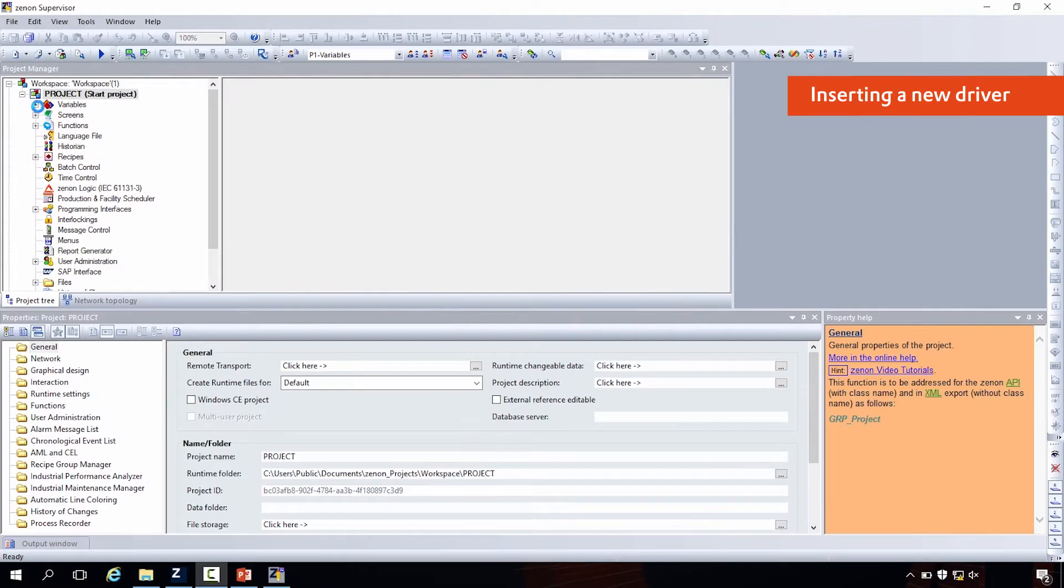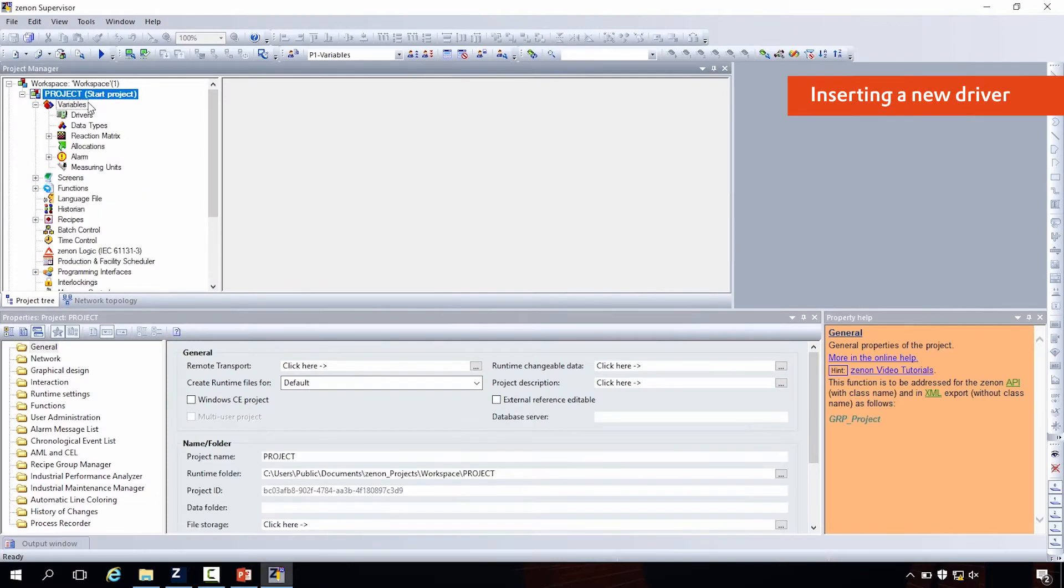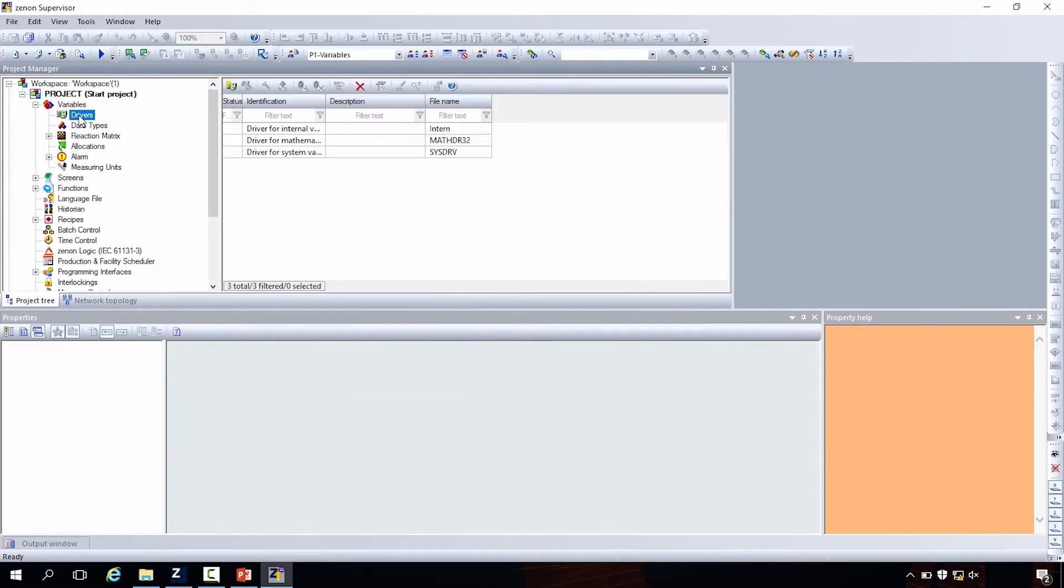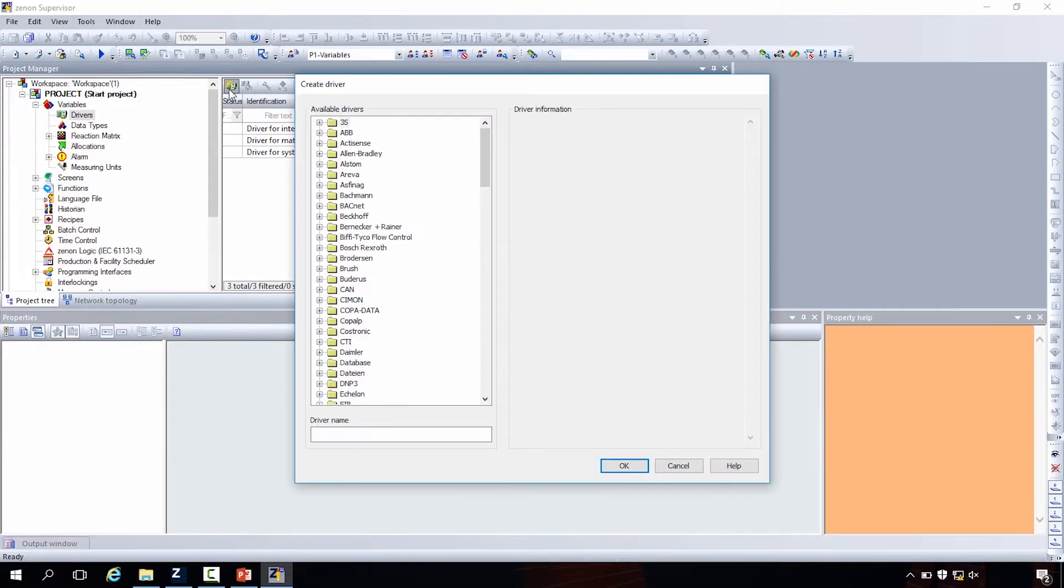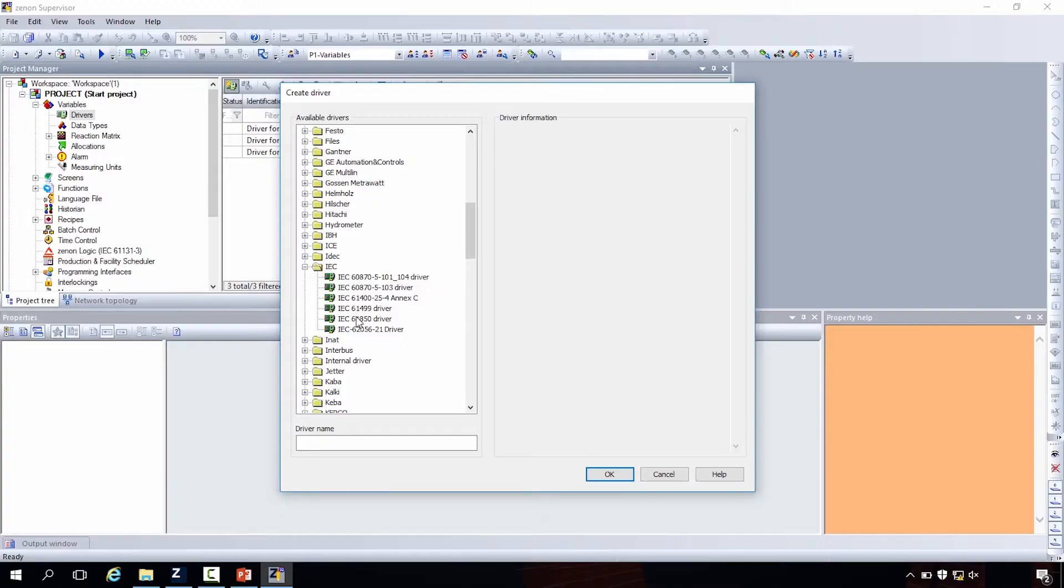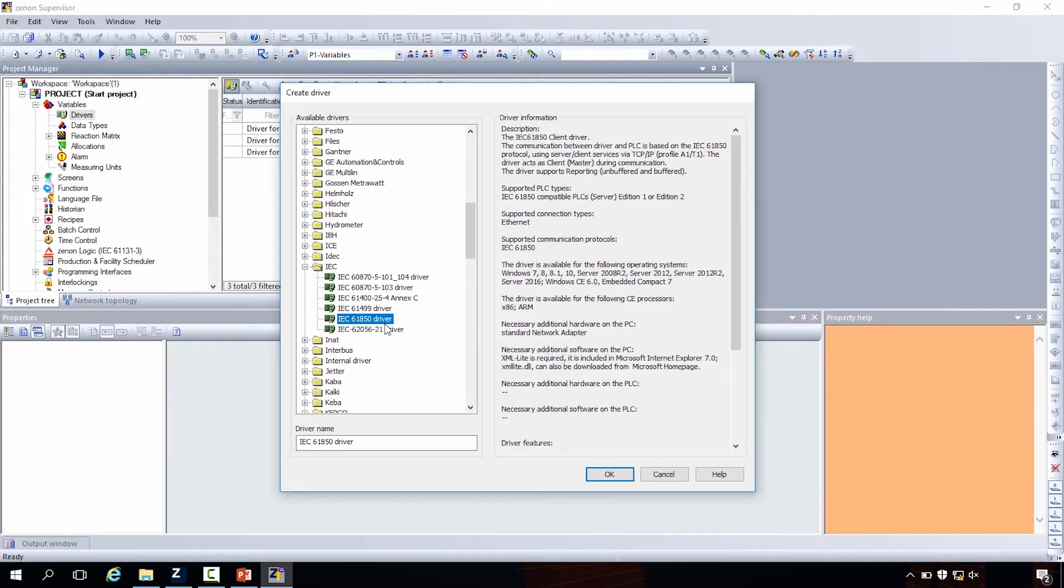So actually in the variable section you find here one branch driver. Here in that driver branch you can create all drivers, the connectivity you need for your project. With a right click or here on the corner, new driver, you can insert a new driver which gives you then the choice of this huge list, all connectivity possibilities in Zenon. And we want to connect now with the IEC protocol, the IEC 61850.